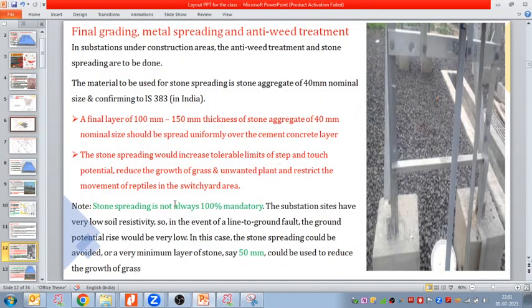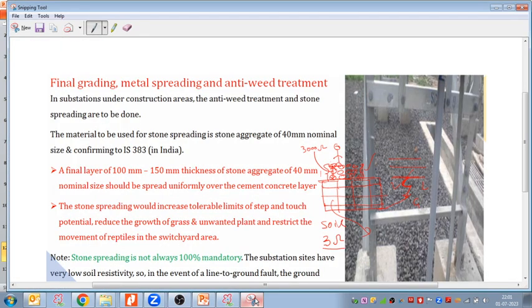Stone spreading is not always 100% mandatory. The substation site where we have very low soil resistivity, in the range of 5, 6, 10 like that - in that range, in the event of line to ground fault, the ground potential rise would be very low. Because we know the ground potential rise is what? GPR.